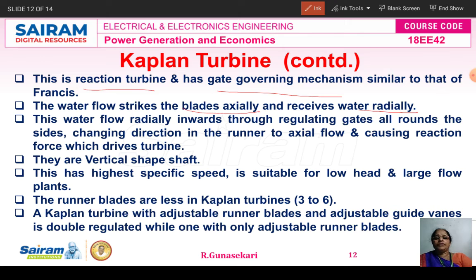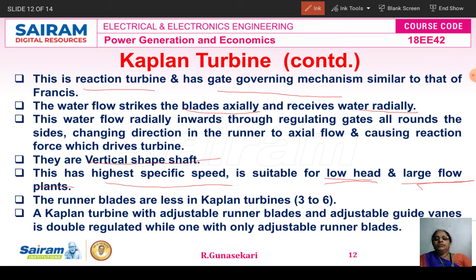The Kaplan turbine uses a vertical shaft. It has the highest specific speed — specific speed being one of the key characteristics of water turbines. This turbine is most suitable for low head and large flow plants. The runner blades are fewer in number — between three to six blades only. The Kaplan turbine has both adjustable runner blades and adjustable guide vanes, providing double regulation, making it highly adaptable.